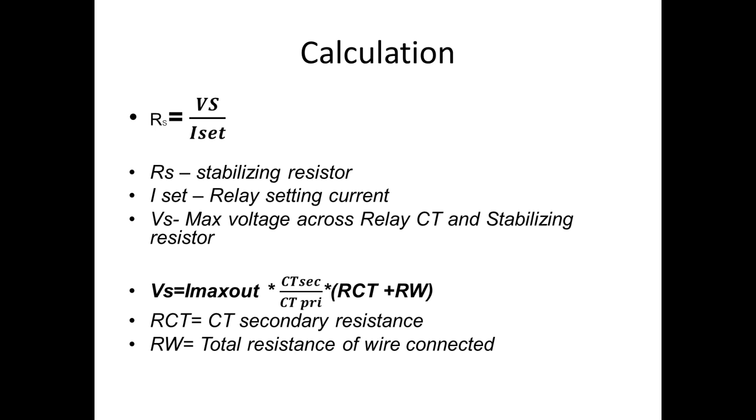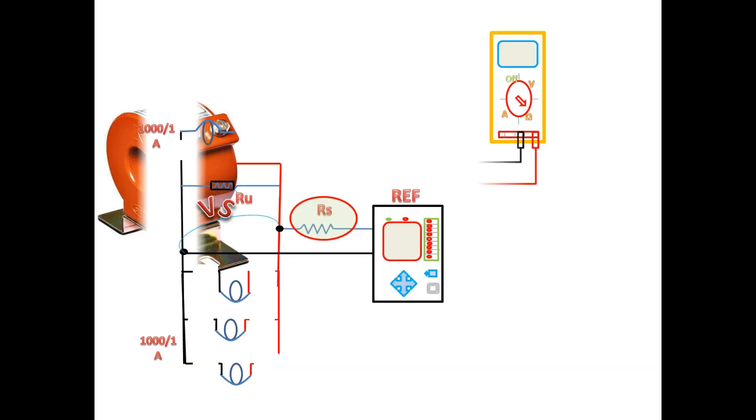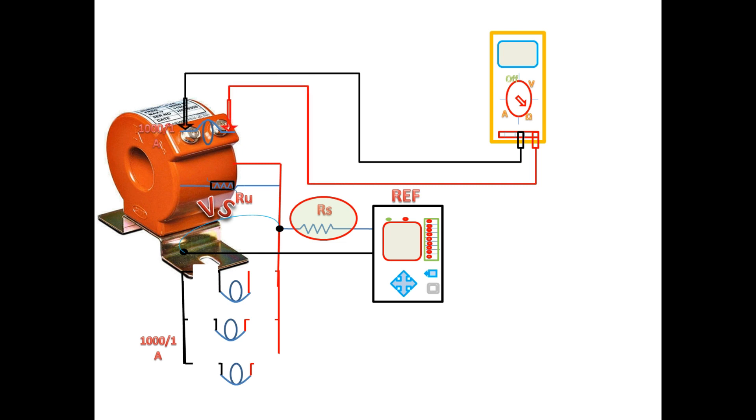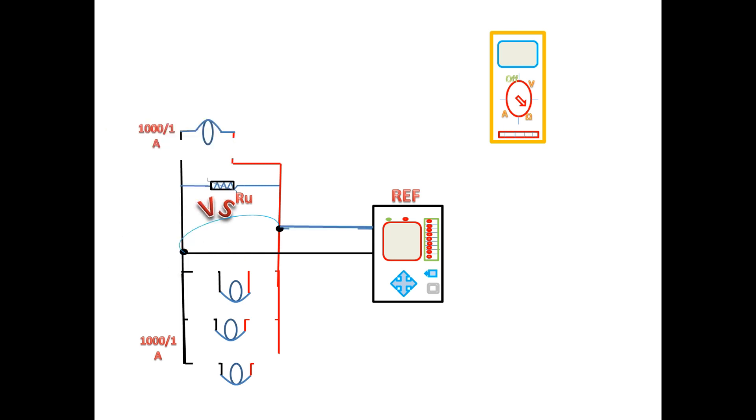To measure this RCT, we have to disconnect the secondary wire to the relay and measure the RCT resistance. RCT is equal to 5 ohms. To measure RW, the total resistance of the wire, we have to disconnect the CT and bypass the resistor RS and then go for measuring the resistor of the wire. We got RW equal to 0.3 ohm.